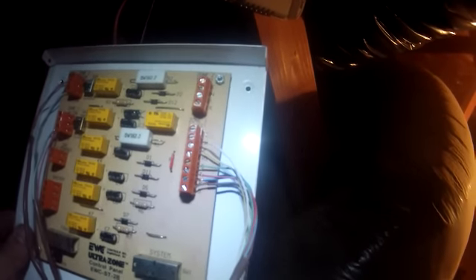Kind of weird that you got W, Y, G, and R, which are your typical connections, but they've also hooked up B and O for, I don't know, heat pump or something, maybe. So this wire that goes back down to the zone 1 thermostat isn't hooked up at B and O, or the blue and brown wires aren't hooked up, just the standard red, green, yellow, and white. So yeah, we won't be hooking B and O up to the new zone board.